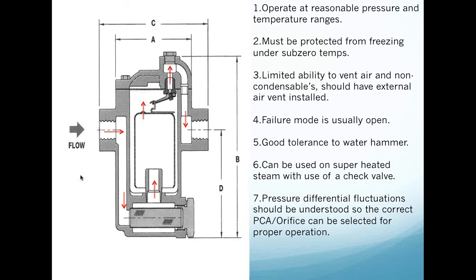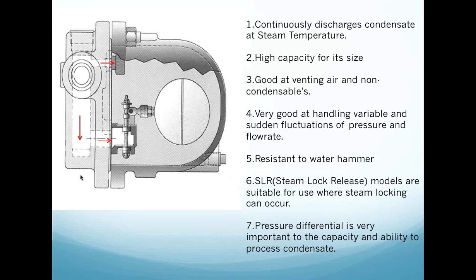So I need you to know what is the maximum pressure differential that one of these traps can see at its maximum condition and at its minimum condition. And I need you all to know: is the system modulating or is it constant? Is the system steam pressure constant or is it modulated? It's a tremendous question that needs to be understood, and you need to ask it. Very, very important. The next trap we're going to look at is a float and thermostatic trap.